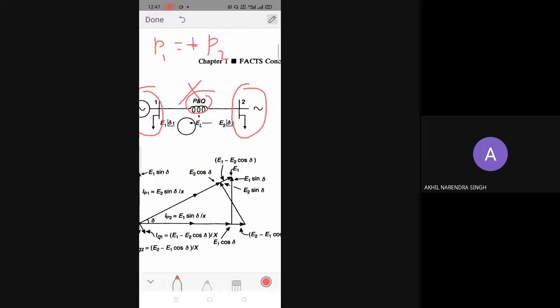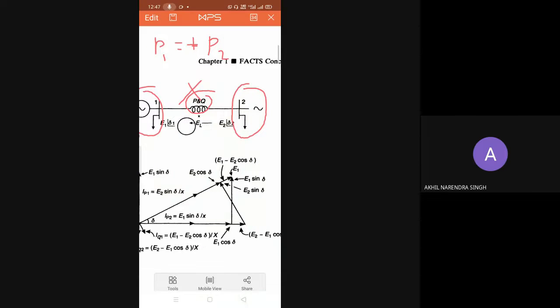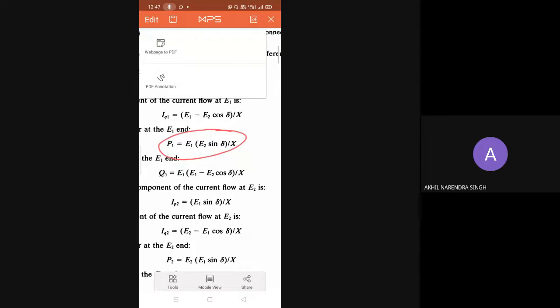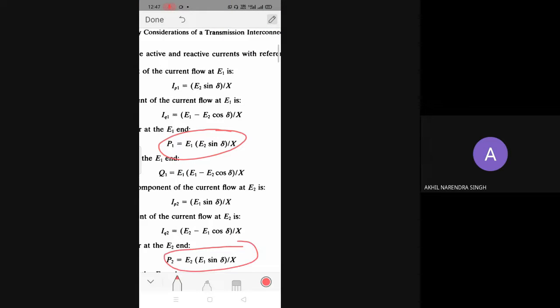So that's why it is negative. If we keep the same definition for both P1 and P2, injected by the region into the line, then in that case P1 is equal to minus P2. But if you change the definition, for P1 real power injected by region 1 into the line, but for P2 real power injected by the transmission line into region 2, then in that case P1 is equal to P2. And it will be the same as the transmission line is lossless, which is equal to E1 into E2 divided by X into sine of delta. That is the same for P1 as well as P2. So as per this, the definition of P1 is different from that of P2. Please try to understand. The definition of P1 is power injected by region 1 into the line, and the definition of P2 is power injected by the line into region 2.